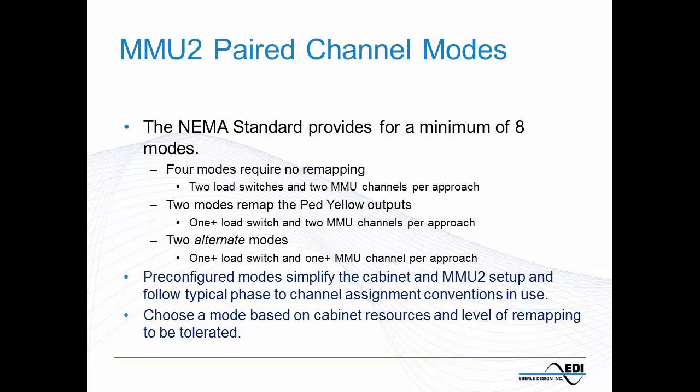Now, I'm going to show you how we go about selecting these modes, but I'll start off by saying the first 4 modes are basically straightforward, 2 load switches and 2 MMU channels per approach. We have a number of cases where we may not have enough load switches available.